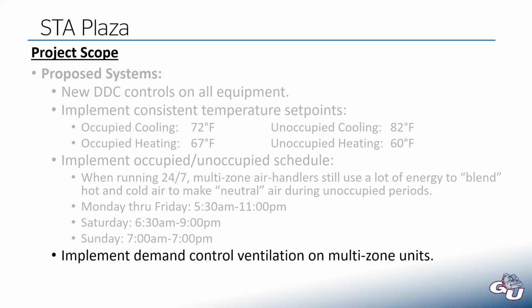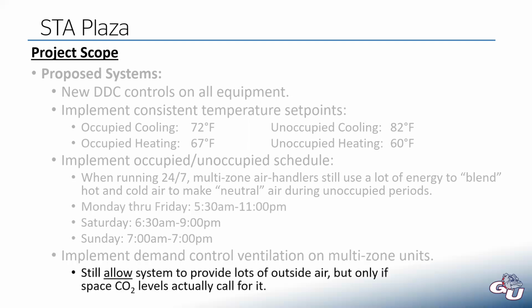The other thing we did is we implemented demand control ventilation. So now we're still going to allow the system to provide lots of outside air. It was designed for 53%, and it is still capable of providing 53% outside air. But with this logic, it's only going to do that if the space CO2 levels actually say we need that much ventilation. And maybe the original engineers had a very good reason for designing it for such a high outside air. But by putting in demand control ventilation, we can heavily trim that back whenever we don't need that much.